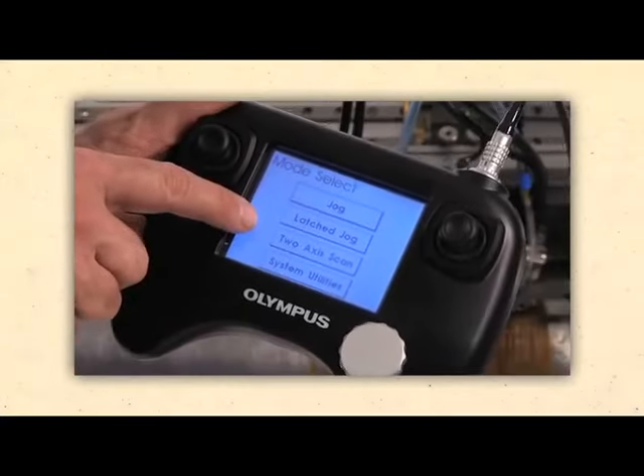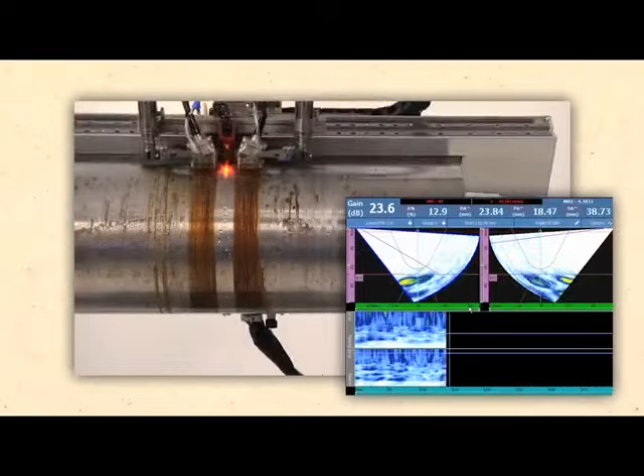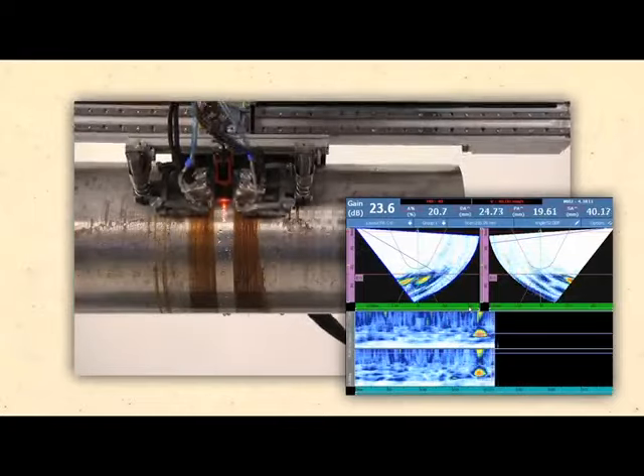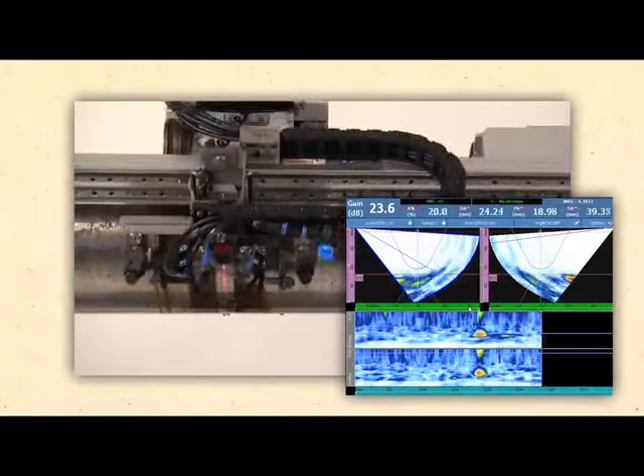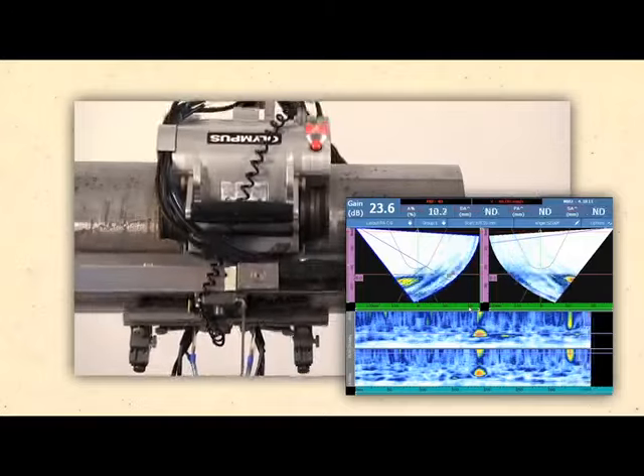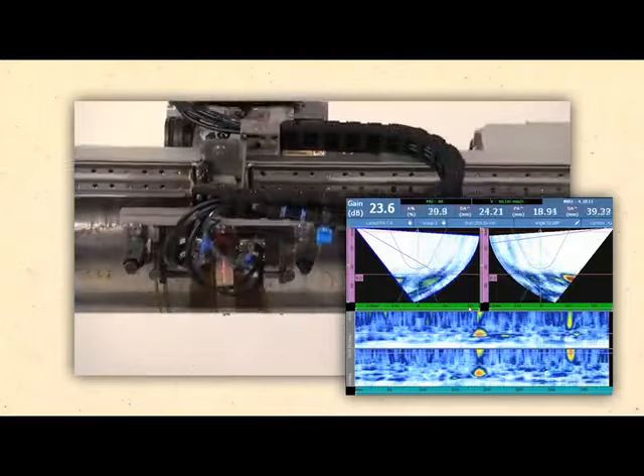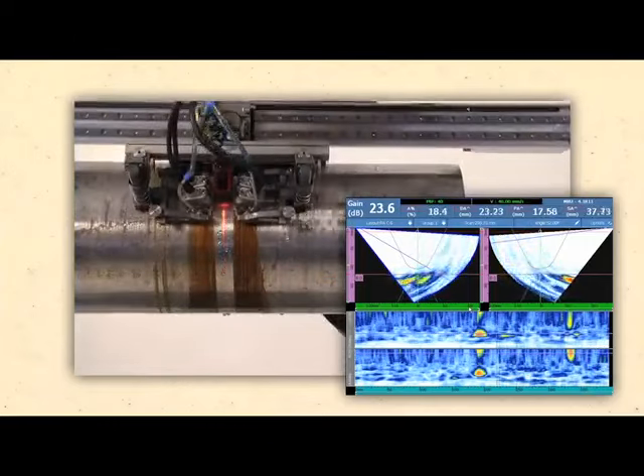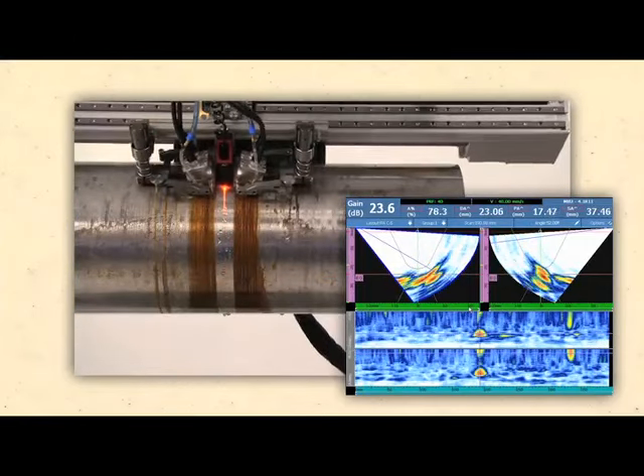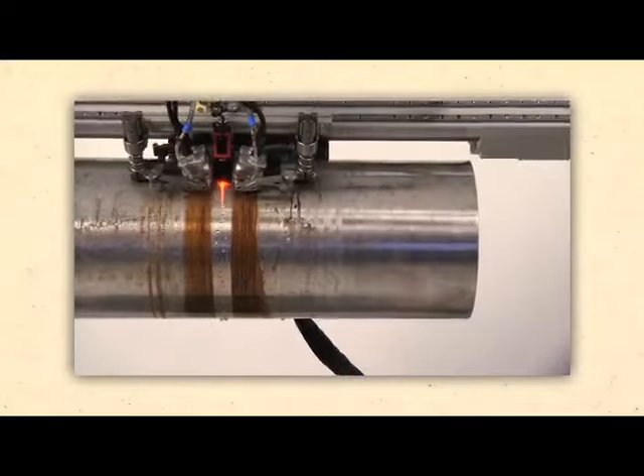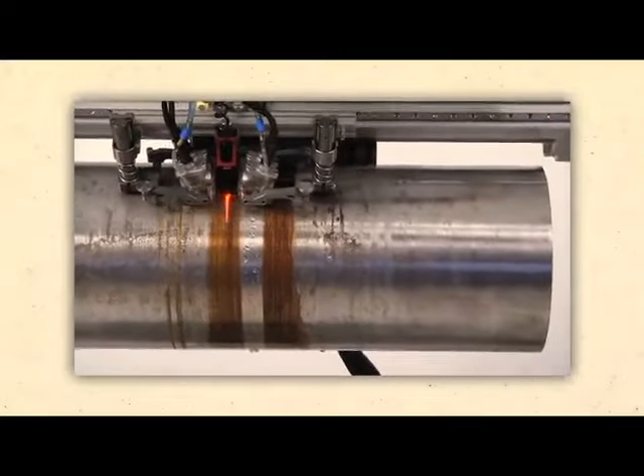A two-axis mechanized scanner provides full automated inspection of CRA welds to include one-line scans for detection and raster scanning for improved flaw sizing and characterization.